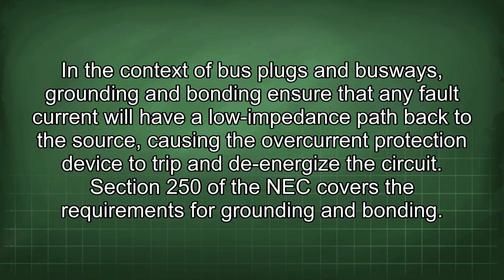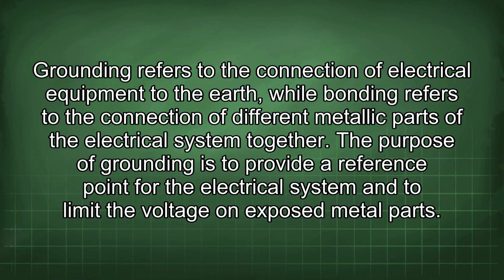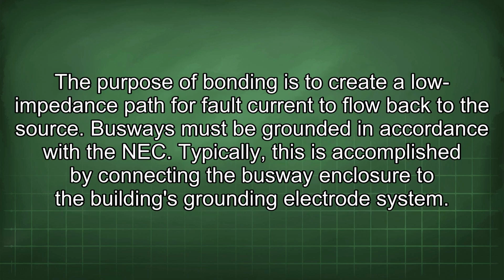Section 250 of the NEC covers the requirements for grounding and bonding. Grounding refers to the connection of electrical equipment to the earth, while bonding refers to the connection of different metallic parts of the electrical system together. The purpose of grounding is to provide a reference point for the electrical system and to limit the voltage on exposed metal parts. The purpose of bonding is to create a low impedance path for fault current to flow back to the source. Busways must be grounded in accordance with the NEC.